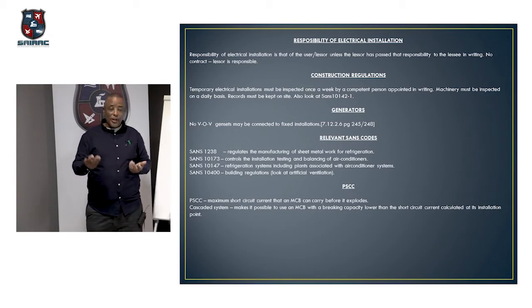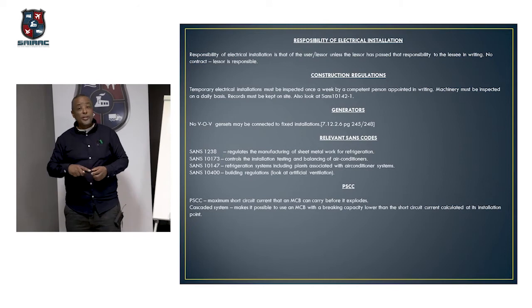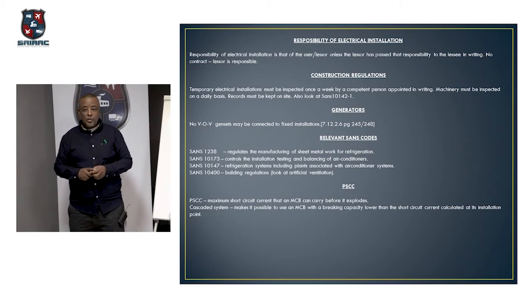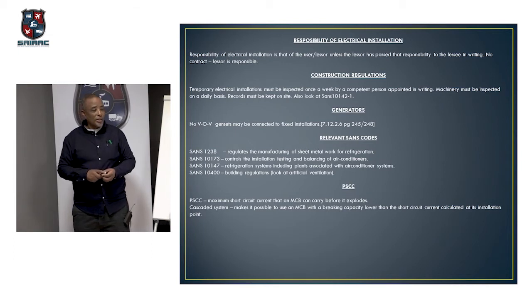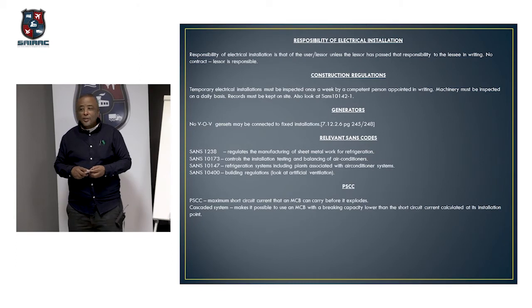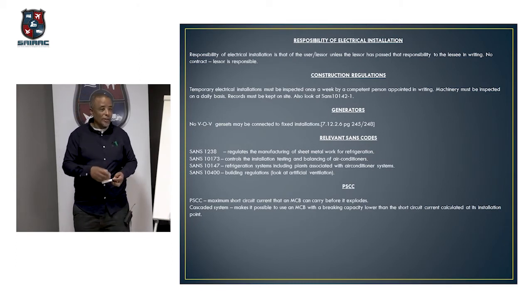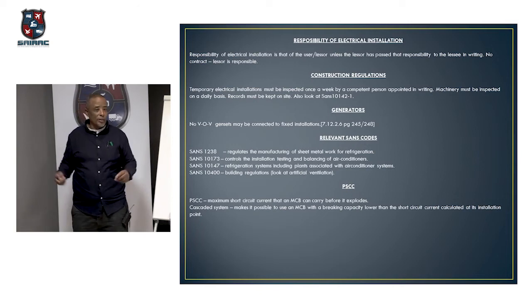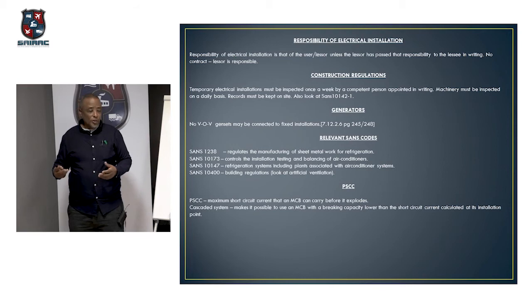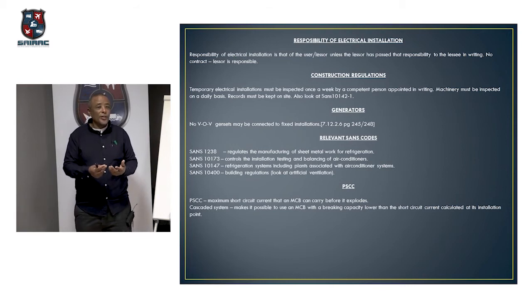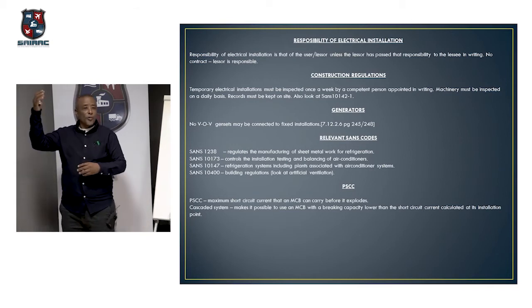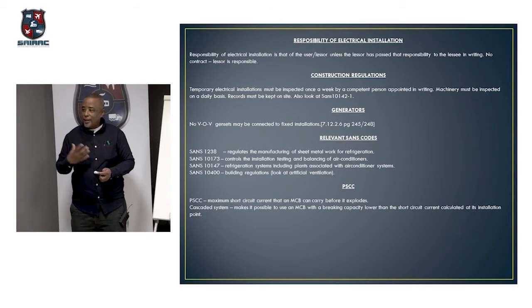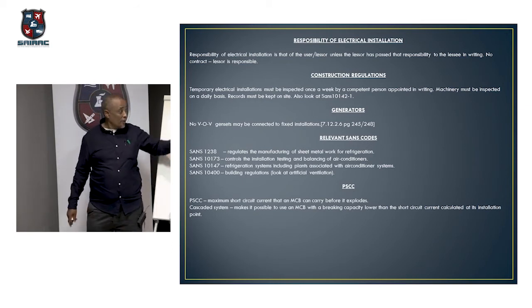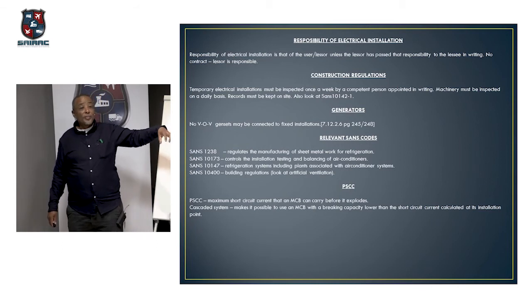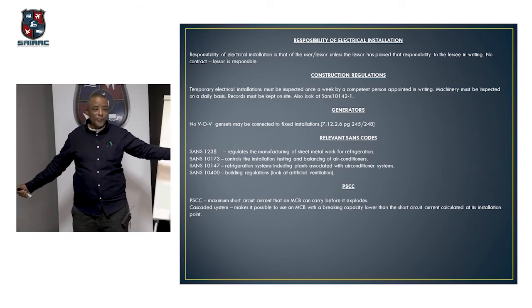But unless it's education, you know, like I just did a block of flats now and I made a guy put occupancy sensors in all the flats. Some flats didn't have windows. So the one client says it's actually a nuisance. I switch it off because I don't like the sound of it. So I said to the contractor, you need to also speak to them and educate them and let them know why it's there and why it must just stay on. The switch must just stay on, because it's going to pick up the body temperature when you move in. It's going to stay on, then when you leave, it will still stay on to remove all the residual moisture. Okay, because then you get infections in the lungs and that type of thing from the moisture. So it's very important, so it's health reasons. So he obviously didn't understand it himself, but I gave him the extract of that. It does say it must stay on for a little while. And the only thing I could think of is occupancy sensor. Nothing else I could think of.